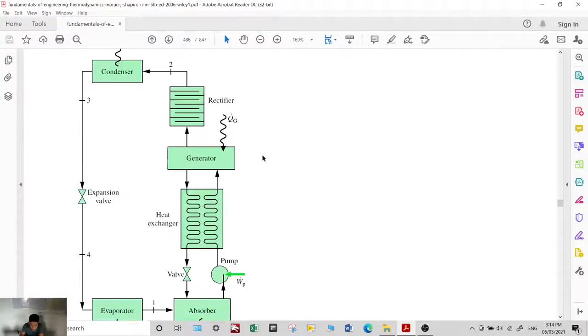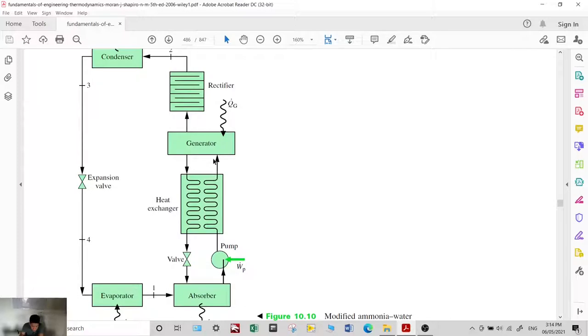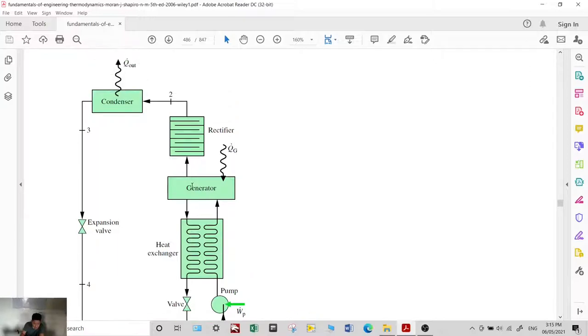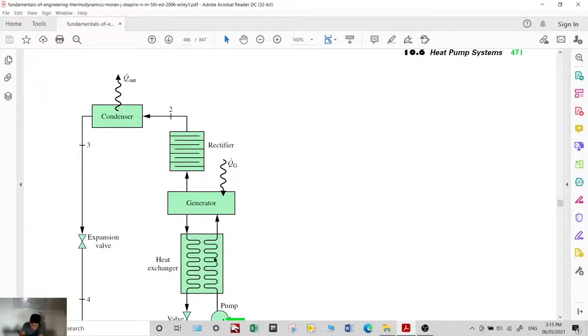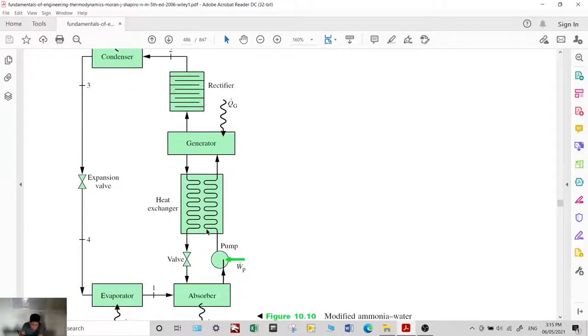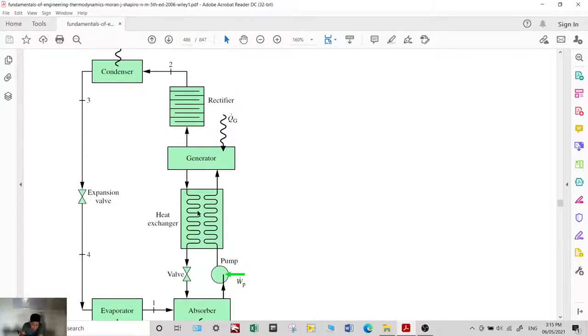A heat exchanger is also added before the valve to pre-heat the solution. The purpose is to pre-heat the solution going into the generator so that less external heat source supply is required in the generator.